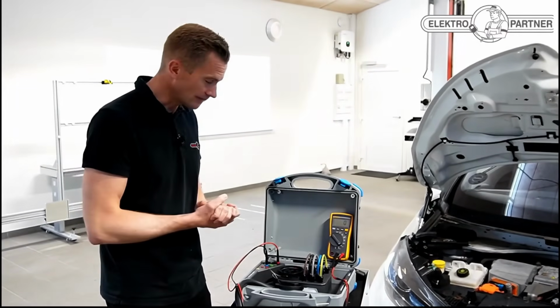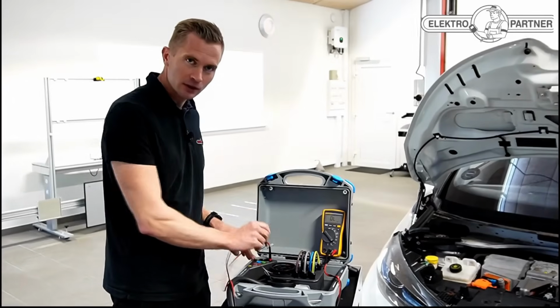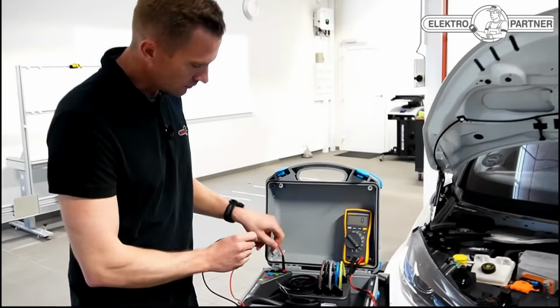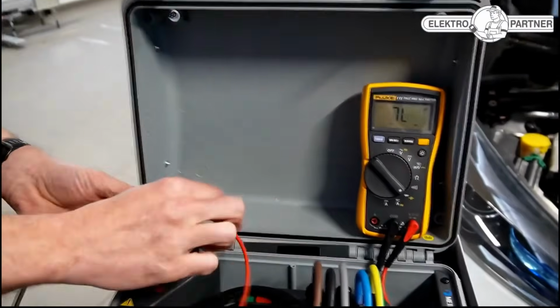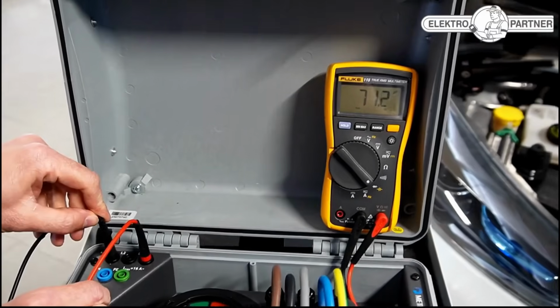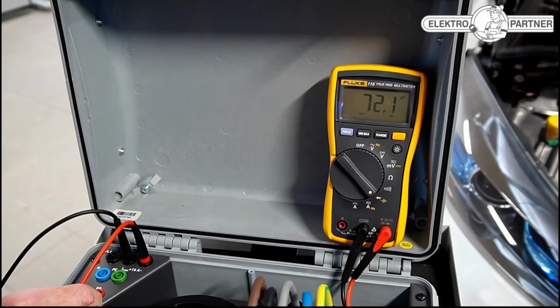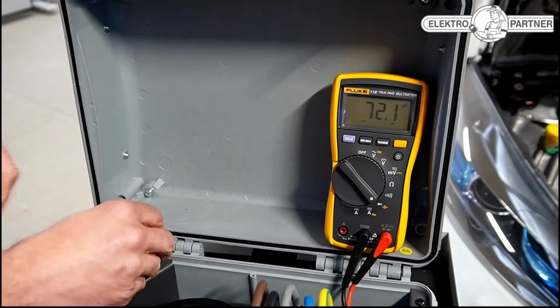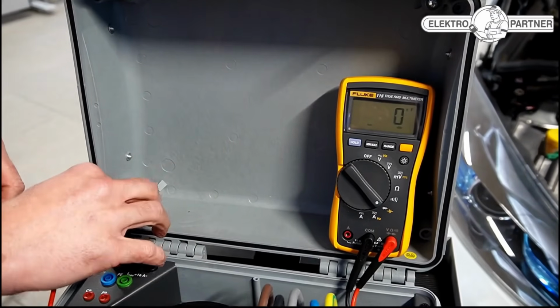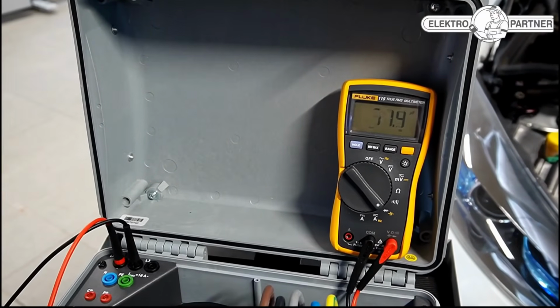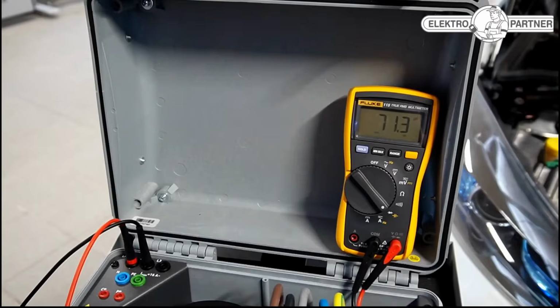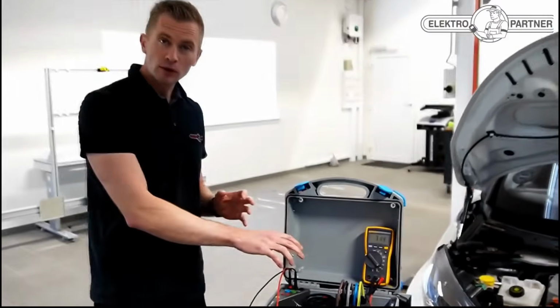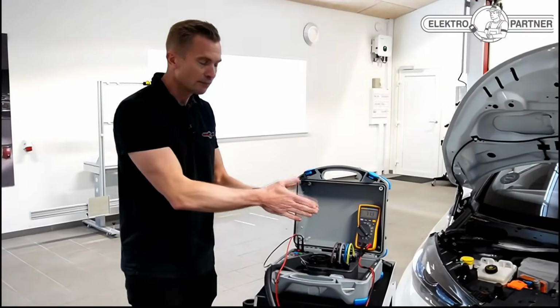The measurement we think could be interesting to do is to measure across the phases instead. So if we test between phase 1 and phase 3, we now measure 71 microfarads. Phase 2 to phase 3, we measure 72, and then phase 1 to 2, 72. So what we wanted to see with this measurement was basically just that we had the same measurement across all three phases.